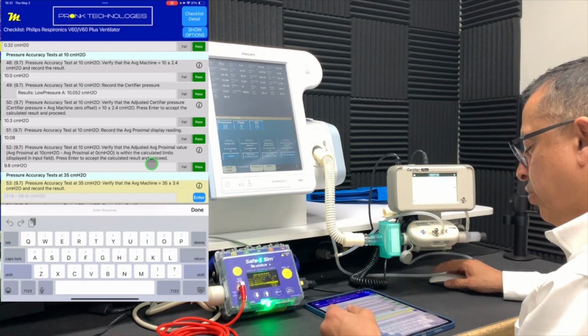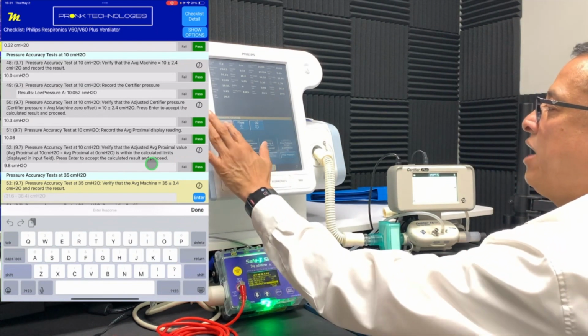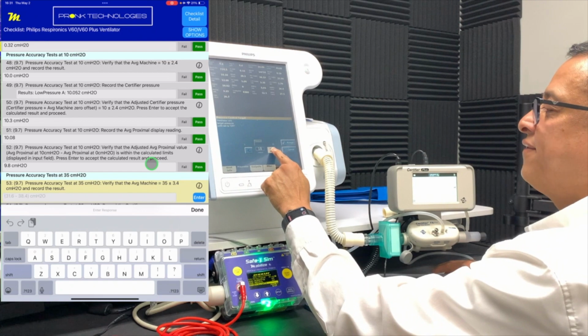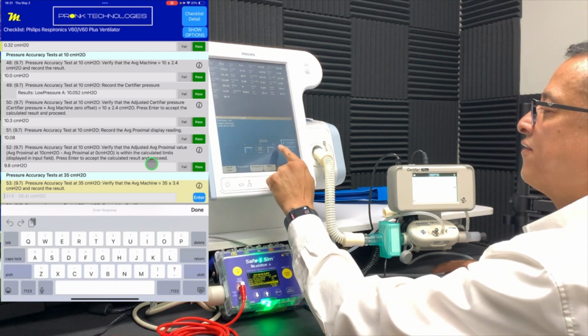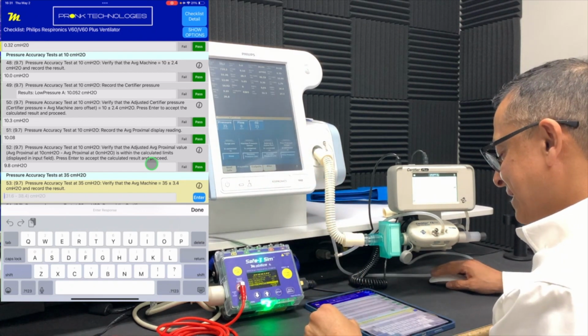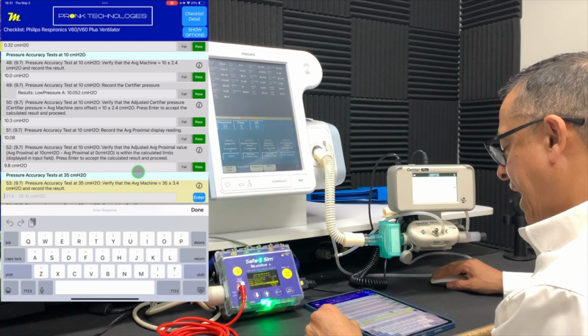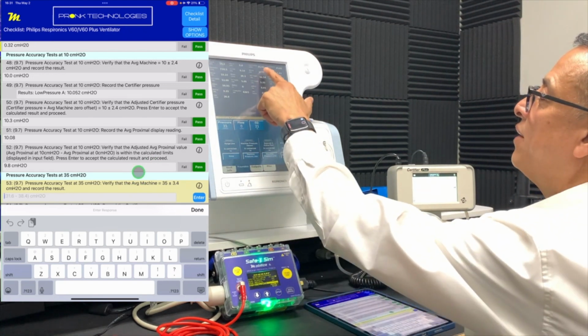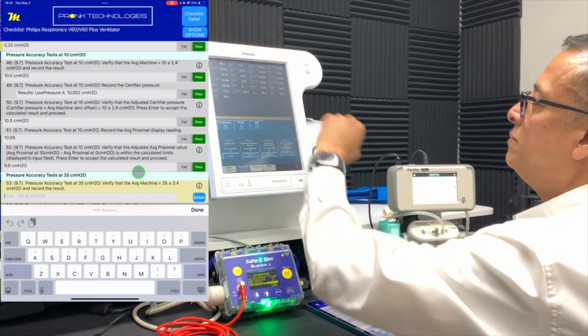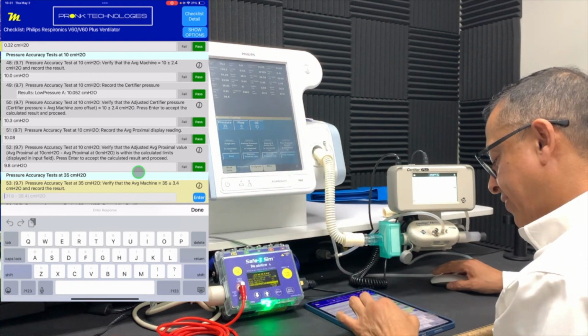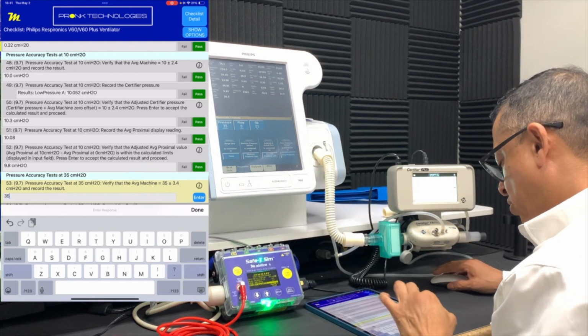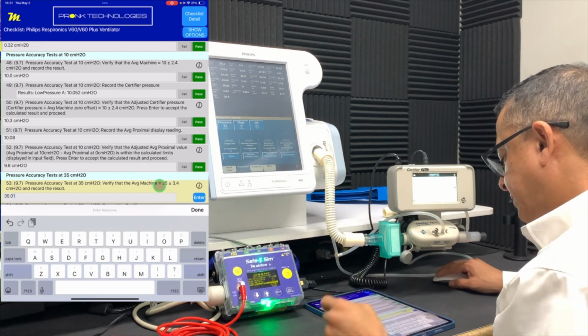So now we're going to go ahead and do the accuracy test at a higher pressure. We're going to go up to 35. We'll go ahead and set the ventilator for that test, and we need to confirm the average machine pressure is within range. So we'll observe it for a moment or two, and it is right at 35.01. Capture that result.